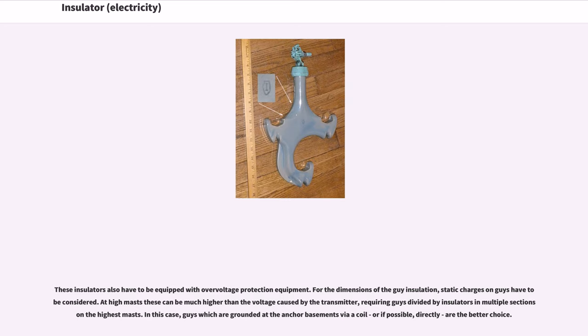For the dimensions of the guy insulation, static charges on guys have to be considered. At high masts these can be much higher than the voltage caused by the transmitter, requiring guys divided by insulators in multiple sections in the highest masts. In this case, guys which are grounded at the anchor basements via a coil, or if possible directly, are the better choice.